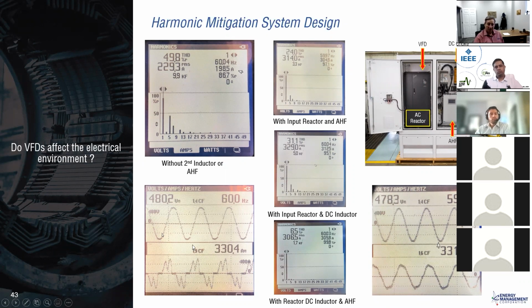That's what the waveform looked like from a current standpoint. You don't see too much flat topping in the current. That's where you start seeing the flat topping on the voltage when it starts getting bad. So we decided we really needed to add more impedance. When we started up the harmonic filter, which is a 100 amp harmonic filter on a 600 amp VFD, in this case it was about a 300 amp load.